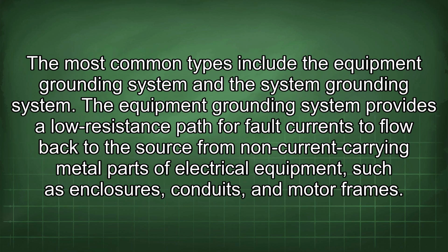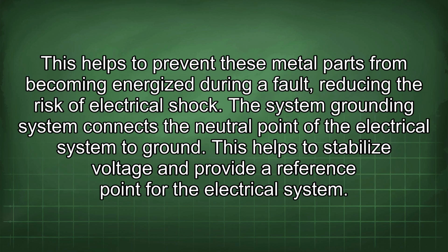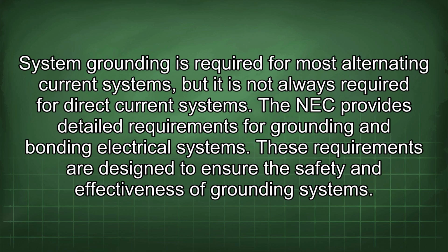There are several types of grounding systems commonly used in electrical installations. The most common types include the equipment grounding system and the system grounding system. The equipment grounding system provides a low resistance path for fault currents to flow back to the source from non-current-carrying metal parts of electrical equipment, such as enclosures, conduits, and motor frames. This helps to prevent these metal parts from becoming energized during a fault, reducing the risk of electrical shock. The system grounding system connects the neutral point of the electrical system to ground. This helps to stabilize voltage and provide a reference point for the electrical system. System grounding is required for most alternating current systems, but it is not always required for direct current systems.